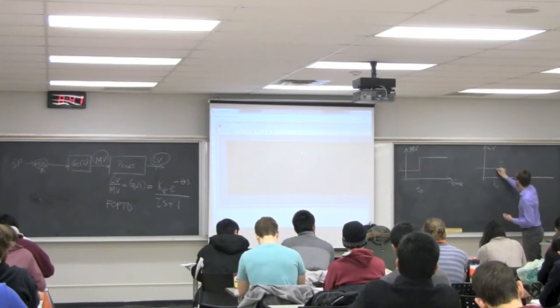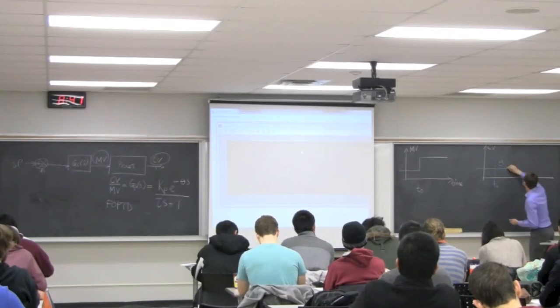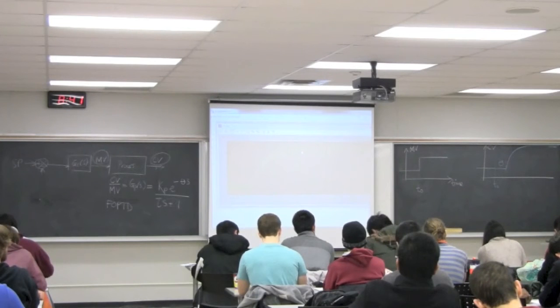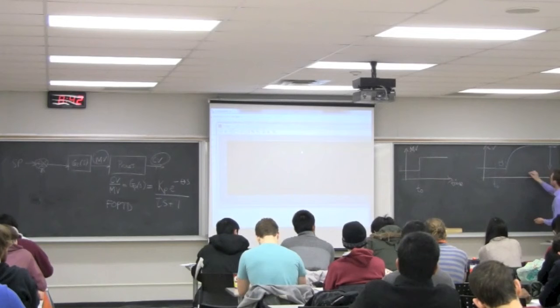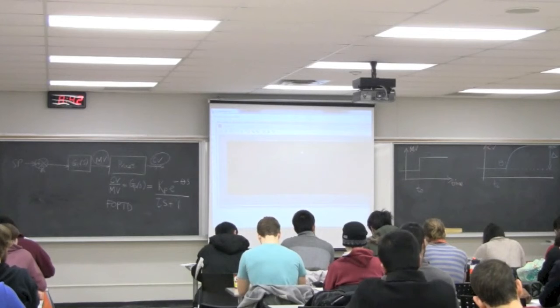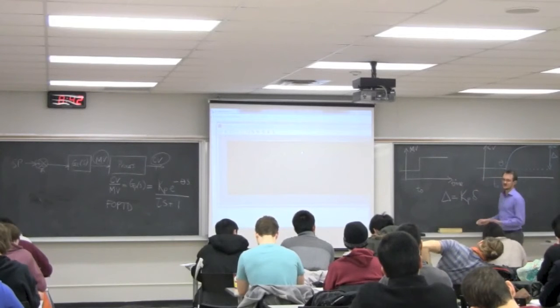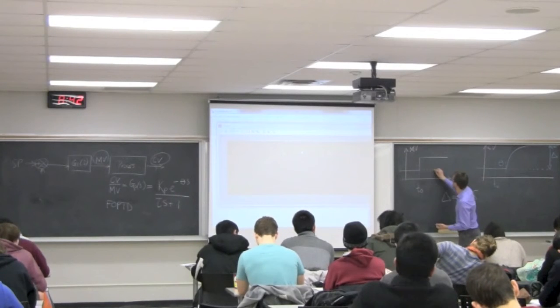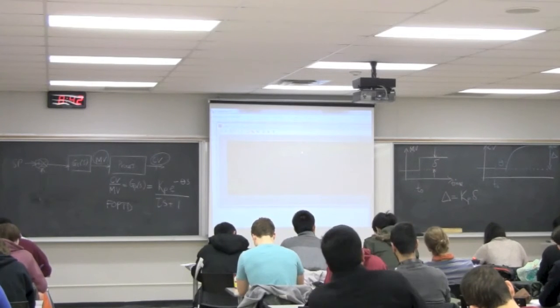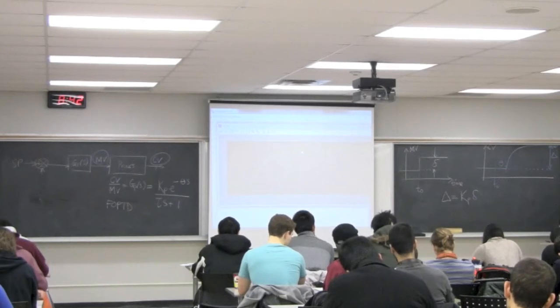Let's draw what we did last time. This is also a good recap. On Friday, we're coming back here to Monday. We said the manipulated variable, I'll make the step change up as follows. That step we said occurs at time t0. My controlled variable, this was the messy plot that we created last Friday. My CV will then respond in a first-order plus time delay manner. Let's take a look at what that should look like. My CV is operating somewhere, and then at time t0, we make that change. We said last Friday that for a first-order plus time delay model, we will actually just keep going at a horizontal line. That's my dead time theta.